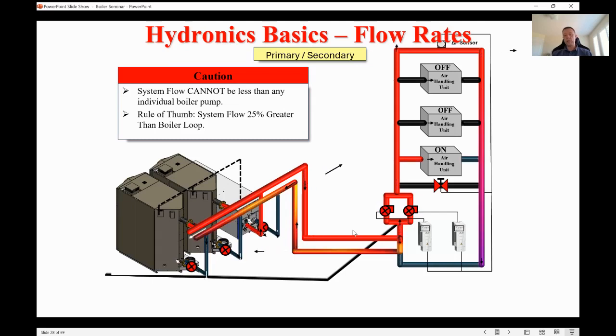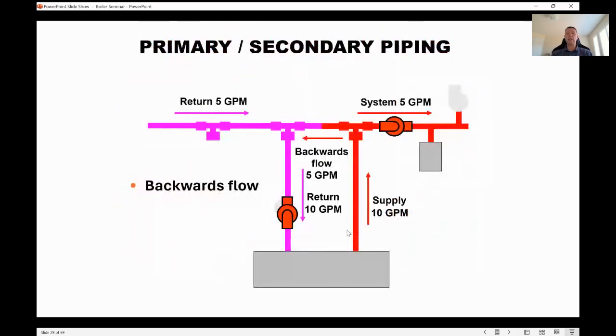What can happen is you can get into a situation where you have more flow in the boiler loop than you do in the system loop. And what happens here is you're going to get some reverse flow. So a lot of that hot water you just heated, instead of all of it turning left, some of it here is going to turn right and go right back into that boiler plant. And you're going to start reheating that water you already reheated, right? This can basically get you into a situation where you're cycling and you can have some issues.